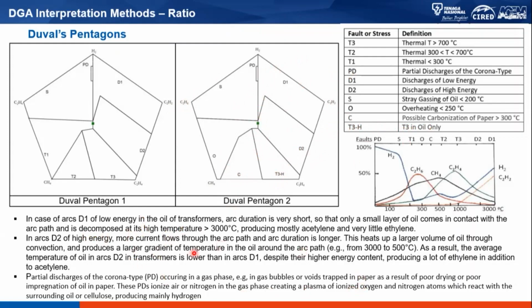One point I'd like to highlight here is the difference between D1 and D2 - discharge of low energy and discharge of high energy. Discharge of low energy, or D1, is defined as an arc of short duration, so that a small layer of oil comes into contact with the arc path and is decomposed at a high temperature of more than 3000 degrees C.